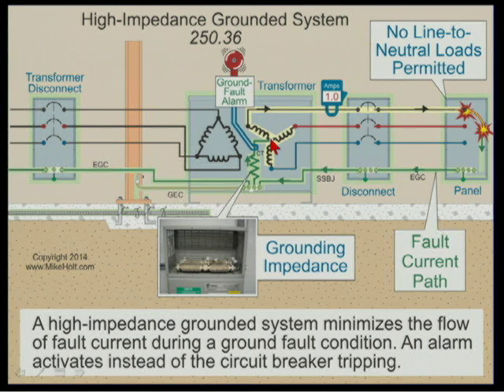However, if you have larger and larger systems, the larger the system you have what is called the charging current. Just simply alternating current moving out and moving in, moving out, moving in, creates a capacitive charge on the conductors. And that charging current could be maybe up to 3 amps. Well, then if you use a 277 ohm resistor and you get 1 amp, and 3 amps of charging current, well, then you're going to have that resistor. It's going to detect more than 1 ampere.